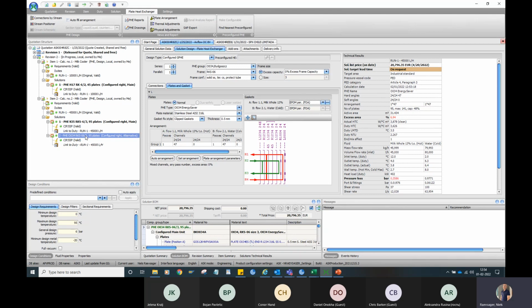We've faced some issues with Orion in sanitary applications, mainly due to leakages on food heat exchangers, because food heat exchangers are subjected to much harder operating conditions than industrial ones. Food heat exchangers are closed, opened, shut down, started up, and so on, so they're subjected to a lot more variation in process conditions. We've had some issues in the past with the Orion starting to leak due to these operational variations, so on a temporary basis we've stopped quoting Orion for food applications.